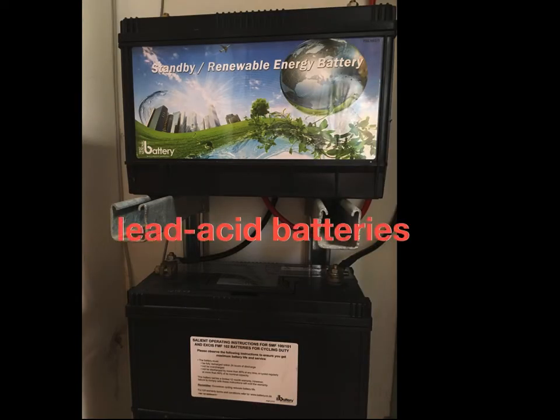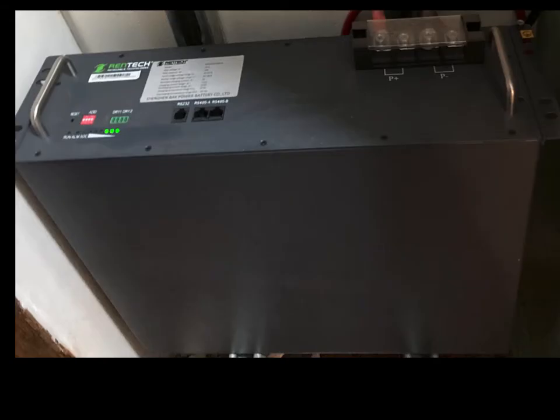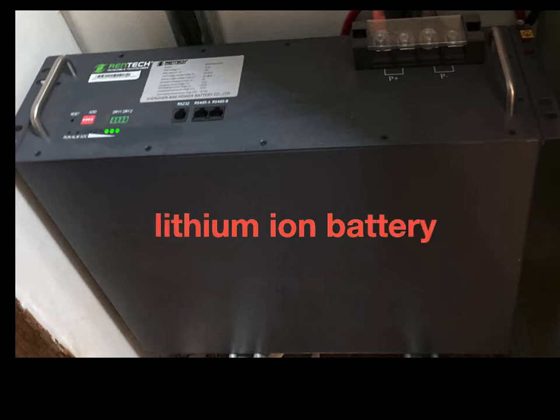Here are the original batteries — lead acid batteries, just like two fairly large car batteries but with slight differences in design so they can take slightly more power drain without killing them. In common with lead acid batteries, their life is limited and the more you drain them, the lower that is. So a few months back I replaced those two with this lithium-ion battery, which is a much better technology. It's essentially the same chemistry as in portable computers and phones but a much bigger one. This particular battery is the same sort of quality used for backing up telecom infrastructure like the cell network. Slotting that in was a fairly straightforward exercise; I made a few adjustments on the control panel but the person who installs it for you should know how to do that.